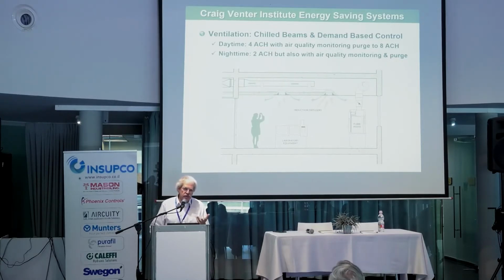But if they sense chemicals in the lab, then obviously they increase it to a higher purge level, typically around 8 to 12 air changes, to clear the air if they sense some contaminants in the environment. So that was the J. Craig Venter lab. That was, again, almost 10 years ago.